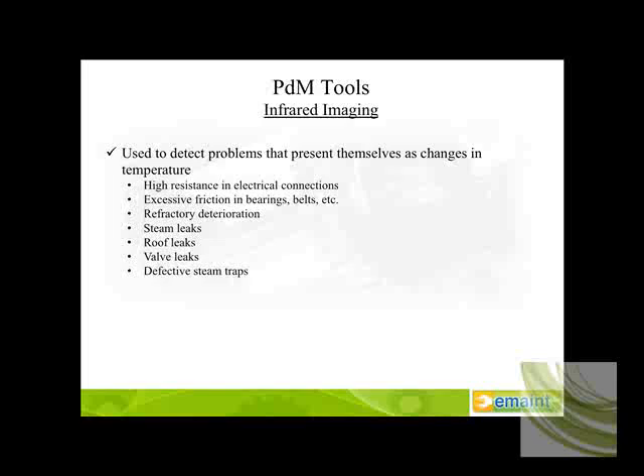Now, by the same token, electrical cabinets can be retrofitted with IR windows. These windows are built in particular crystallines. Calcium fluoride is one of them, and they are relatively transparent to the infrared energy seen by an infrared camera. So while we do need to take into consideration our arc flash requirements on medium voltage, high voltage electrical gear, there's also the capability of installing these IR windows so that you can still monitor the electrical system fully all the way down through your electrical system.